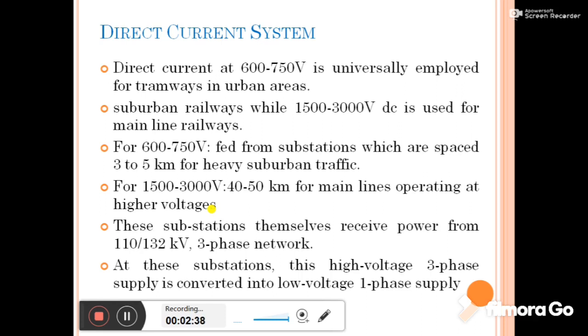If electrical traction is 1500 to 3000 volt DC, substations are spaced 40 to 50 km apart for main lines operating at higher voltages. So for 600 to 750 volt the distance is 3 to 5 km, but for 1500 to 3000 volt it is 40 to 50 km. Why is there less distance in one case and more in the other?